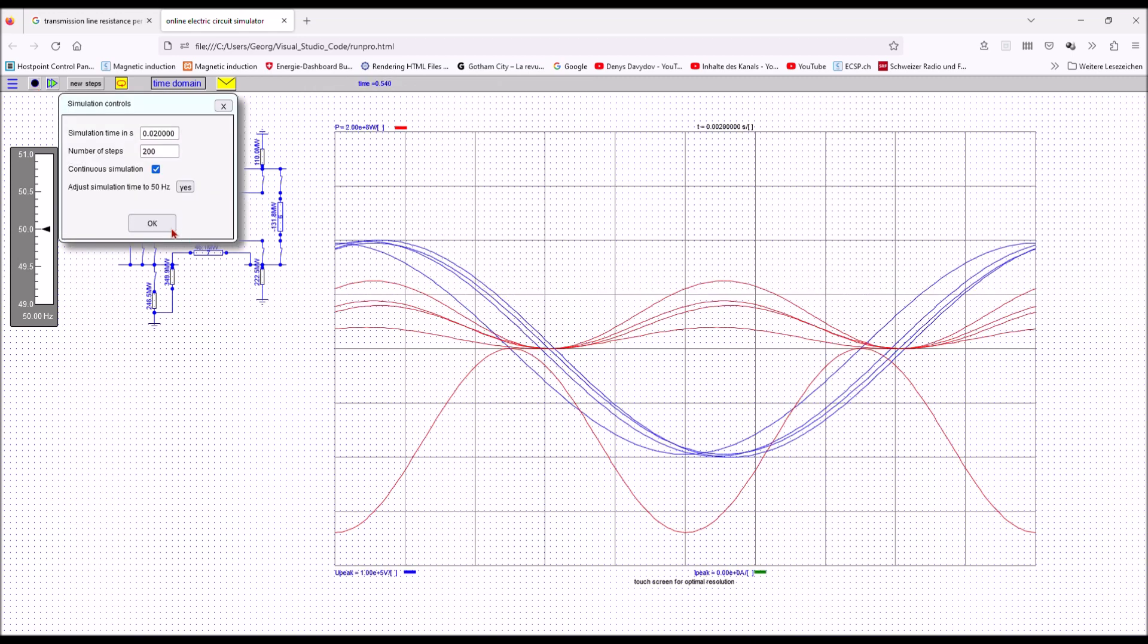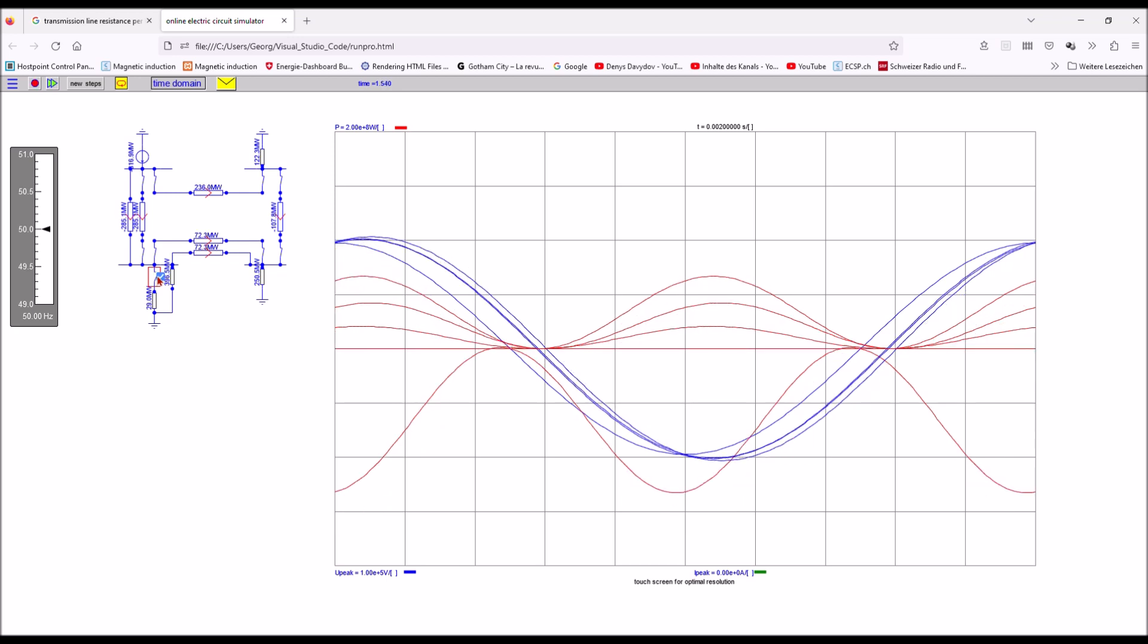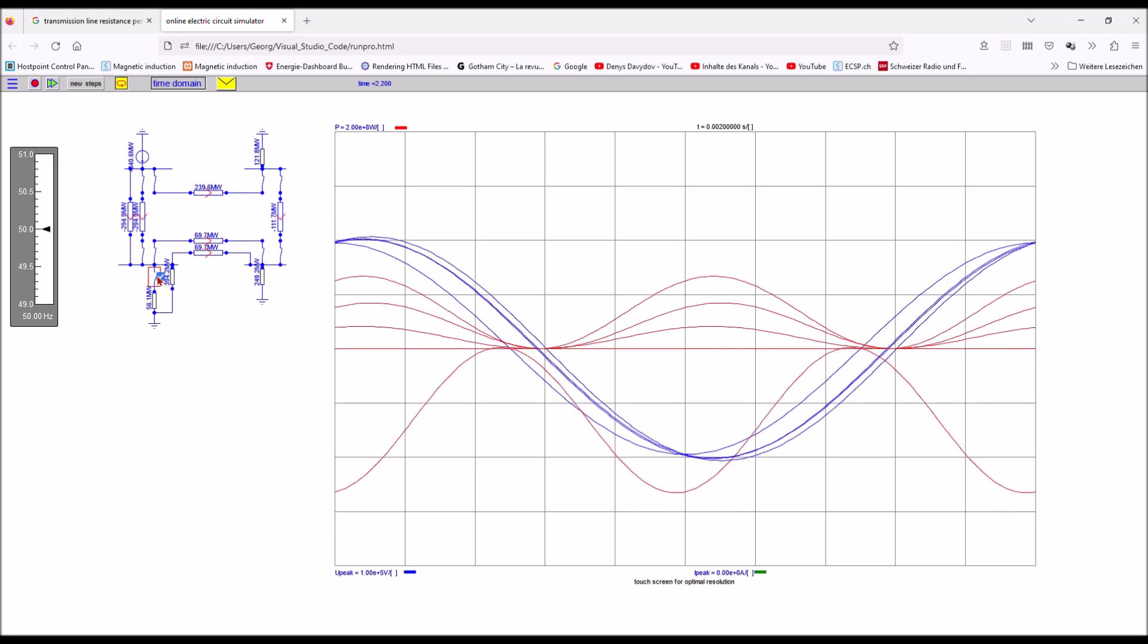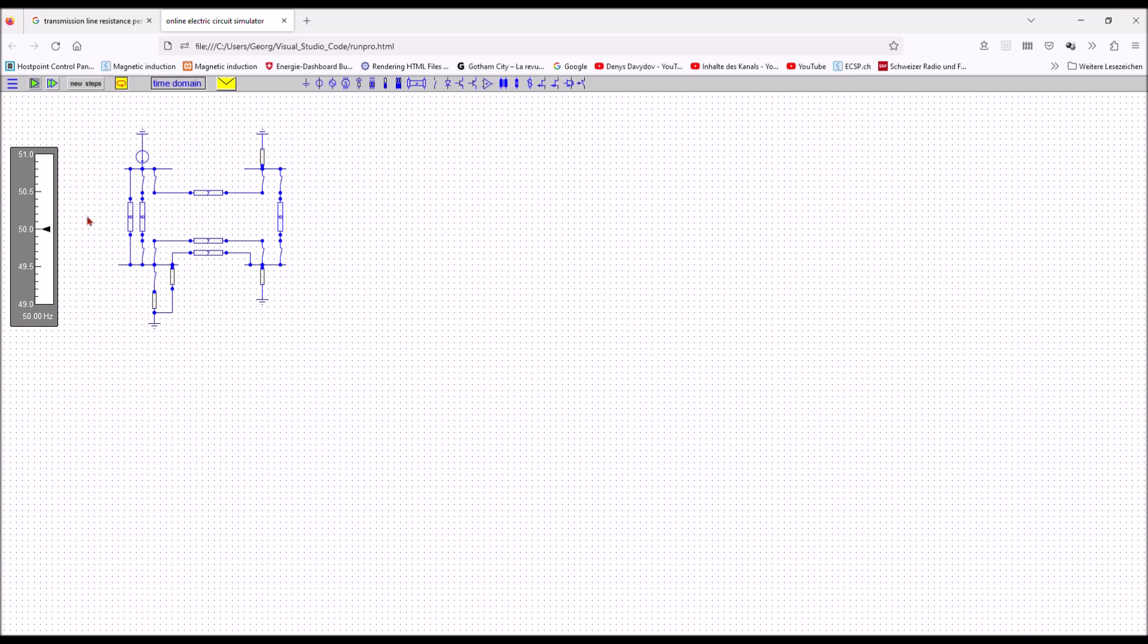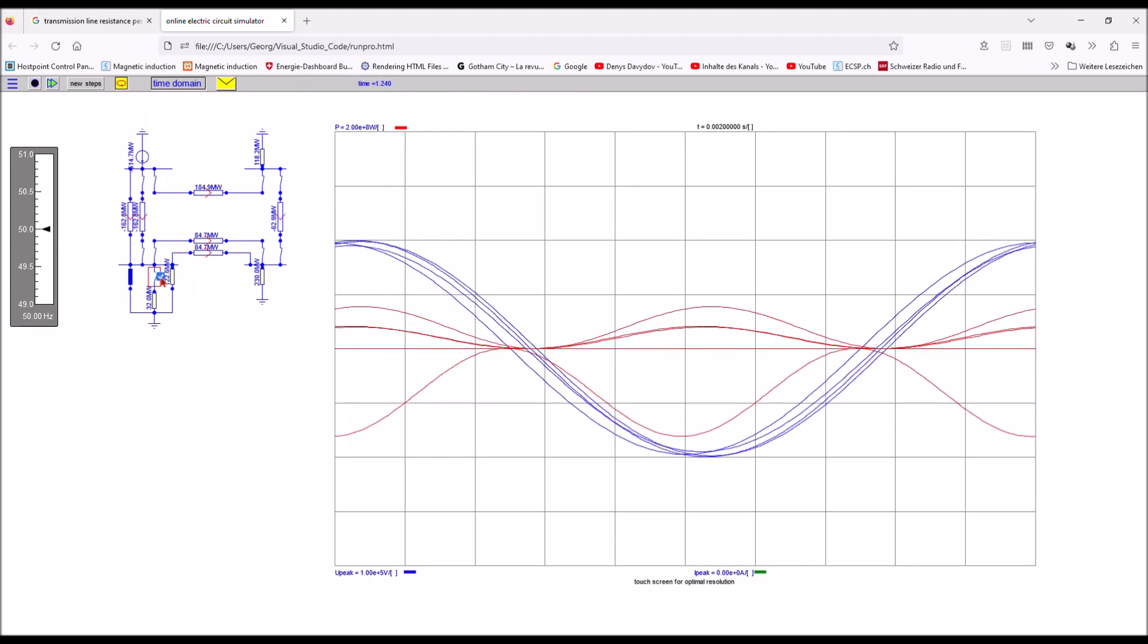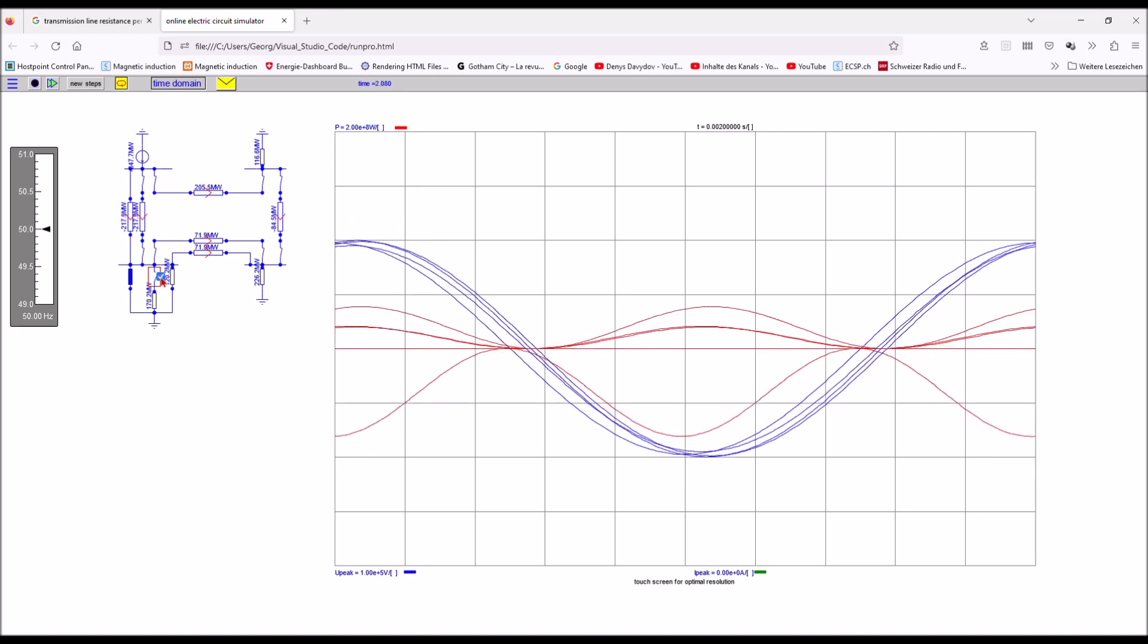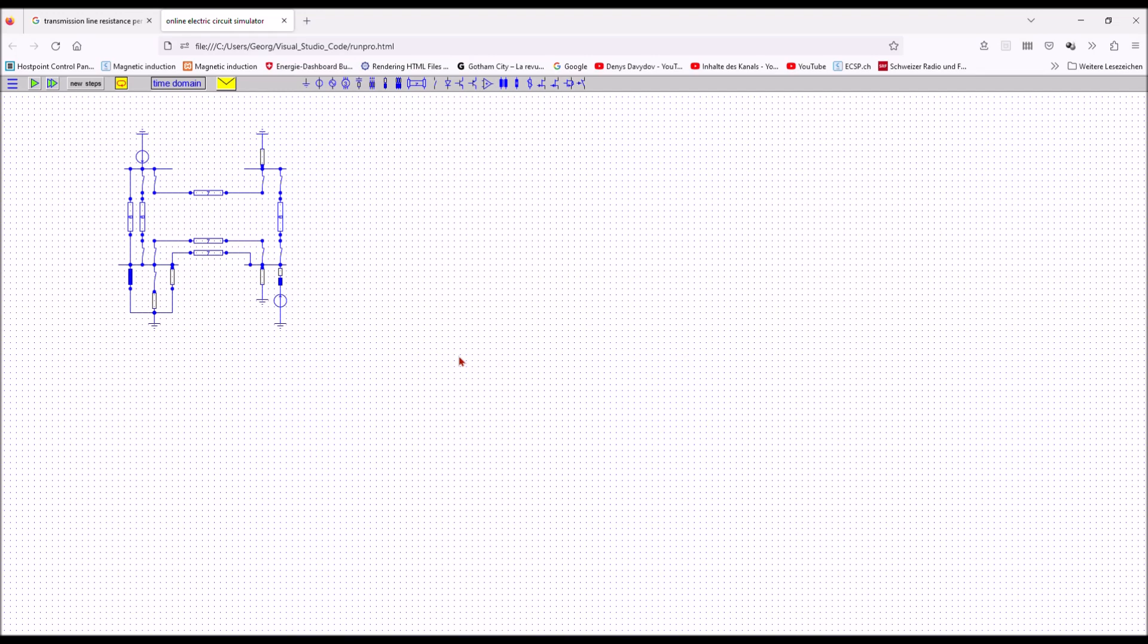If I lose a part of the load I get slight over voltages. This is due to the capacitive characteristics of the connected power lines. The voltage stability band is very narrow therefore a reactive power compensation is needed. The reactor compensates the capacitive currents of the power lines and as you can see the situation has already greatly improved. In reality I would have to optimize the compensation at all the nodes.